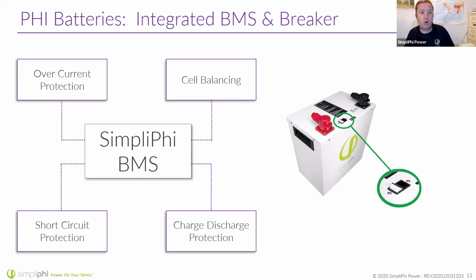If it gets too cold, the battery management system in the SimpliPhi batteries can tell pieces of equipment to slow down charging rates, and at some point even stop charging. So the more advanced battery management system is nice because it's able to communicate pre-programmed set points into pieces of equipment, offer that cold weather protection, and tell those inverters and charge controllers what its state of charge is.